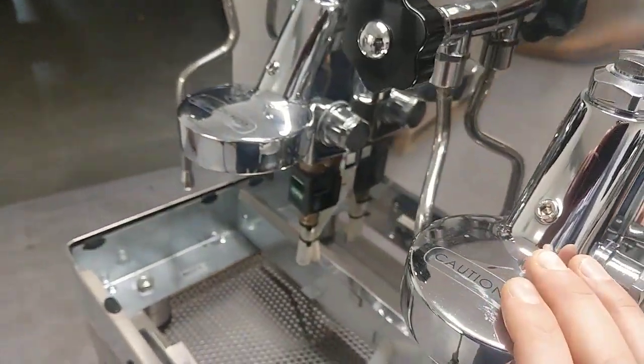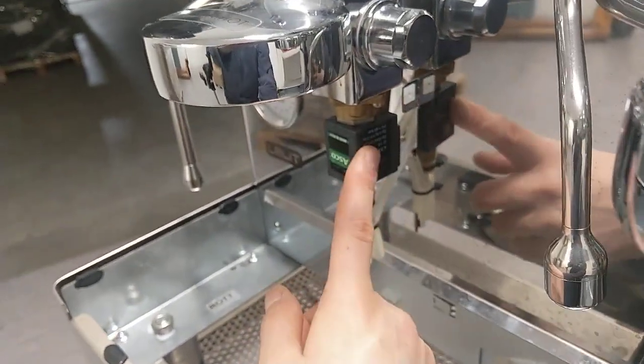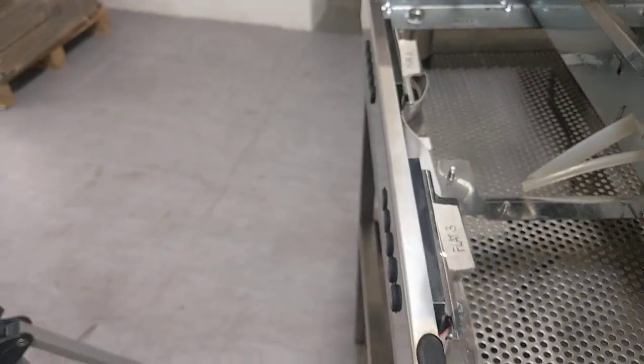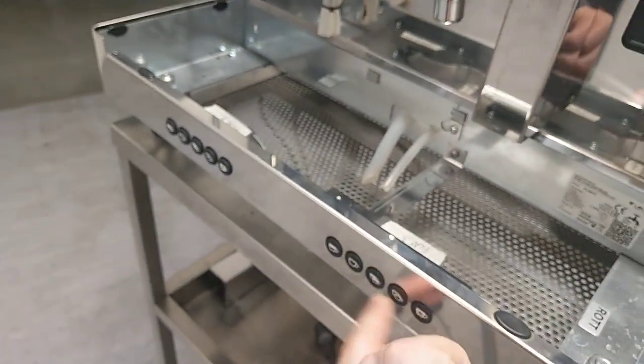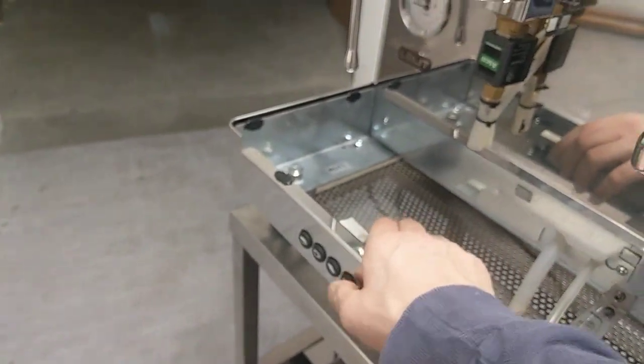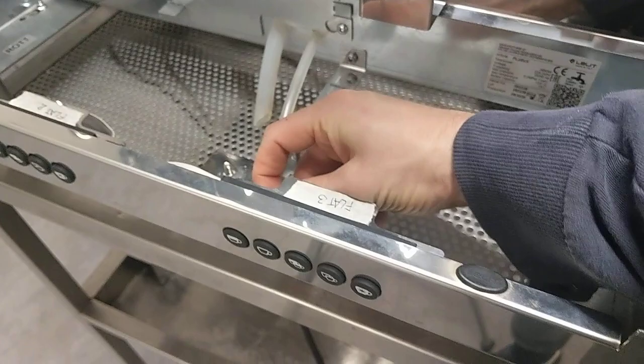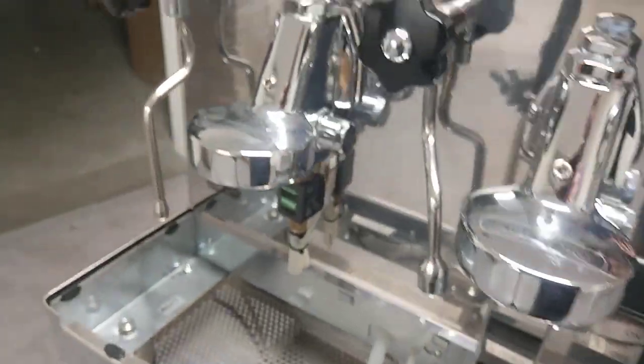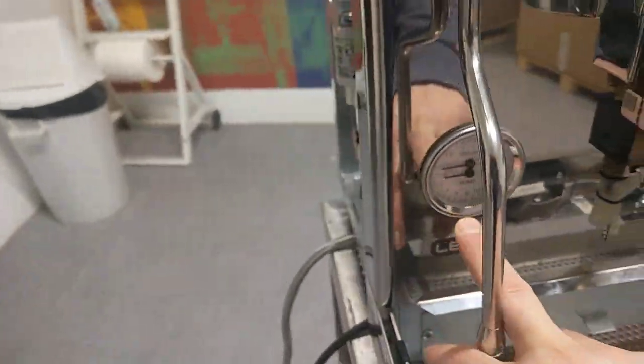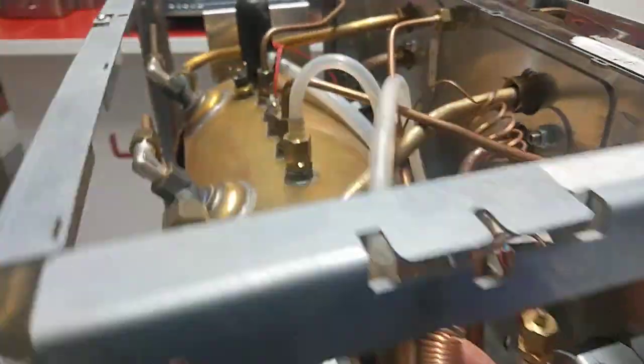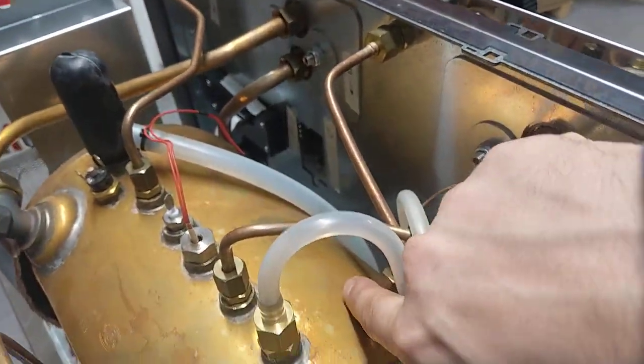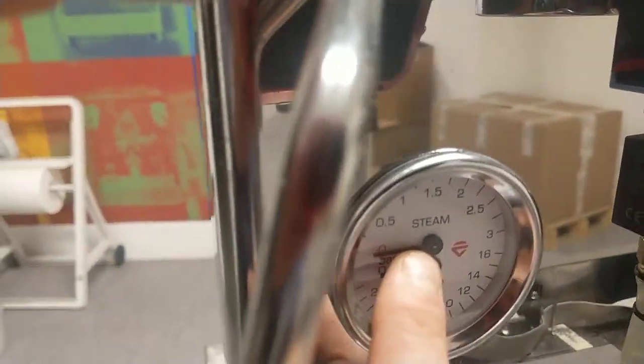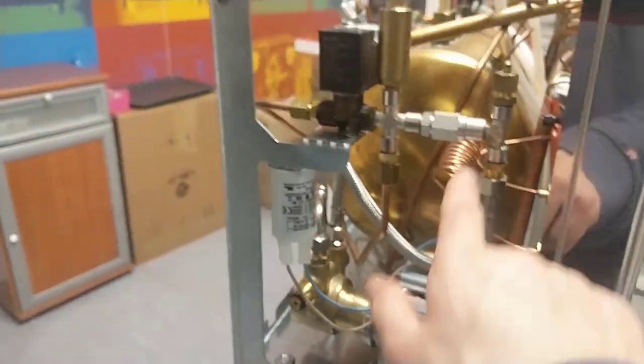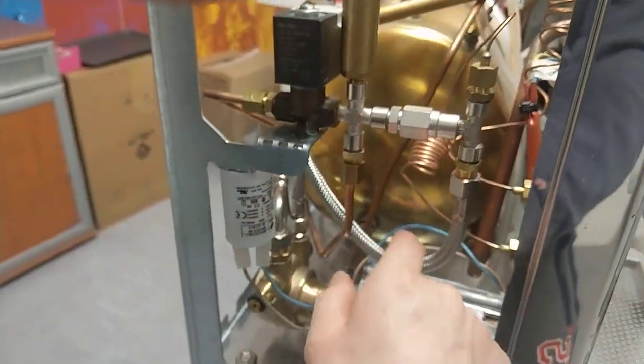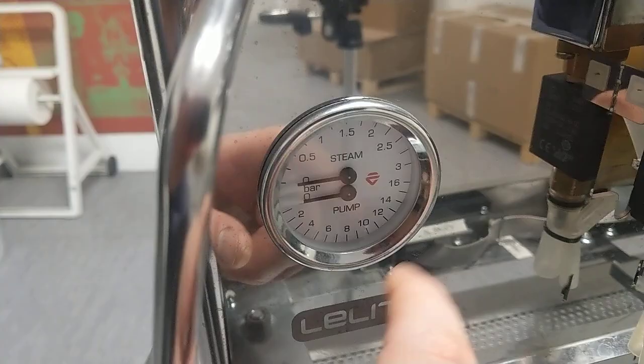Water tap, brew group, three-way solenoid valve, and this is the button for the doses, and you can set the amount of water we want here. After that, the last is the pressure gauge. It's connected on this side, on the top of the boiler for the steam, and here, as we can see, we have the pump, and the second is connected here, and it detects the pump pressure.